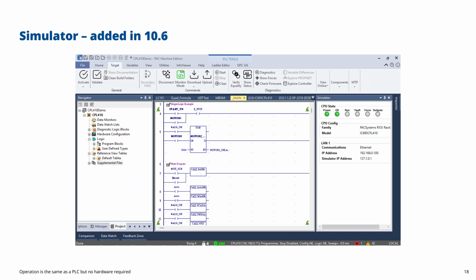Also, because the real machine has real-time delays, I had to use a lot of timers in my simulator, otherwise everything would run so fast I wouldn't be able to view it. For example, when the output turned on, I'd have to wait a few seconds, implementing a timer before that device actually started, to simulate running a conveyor, opening a valve, or whatever. So the simulation is certainly possible, but it can be a bit complicated. Again, it's a great way of testing things before you get to your machine.